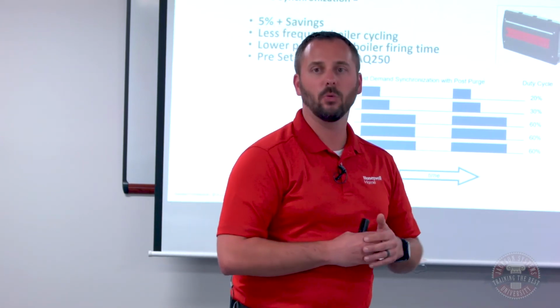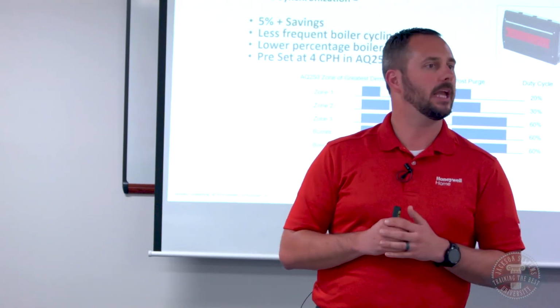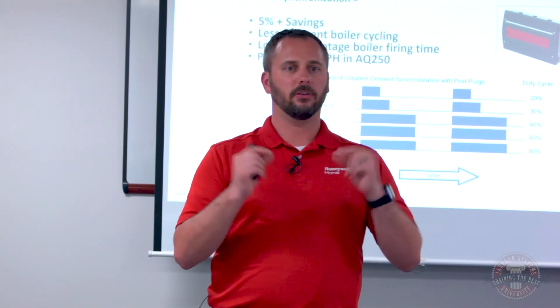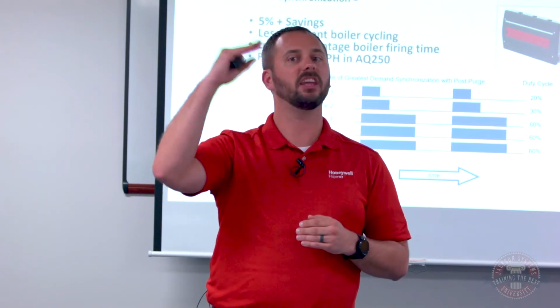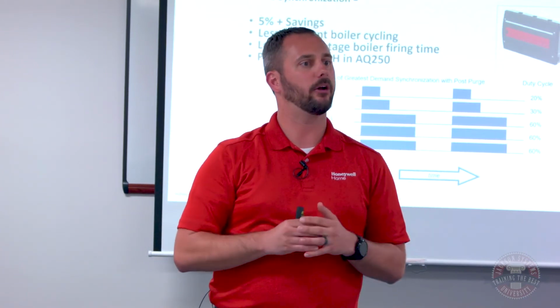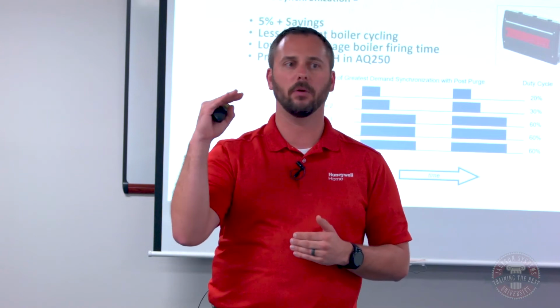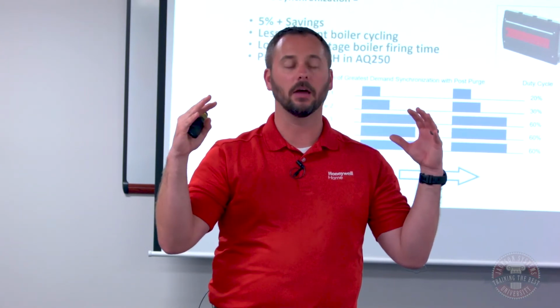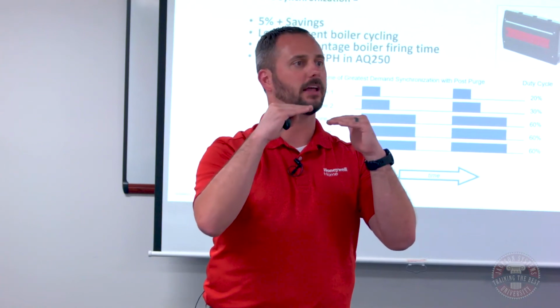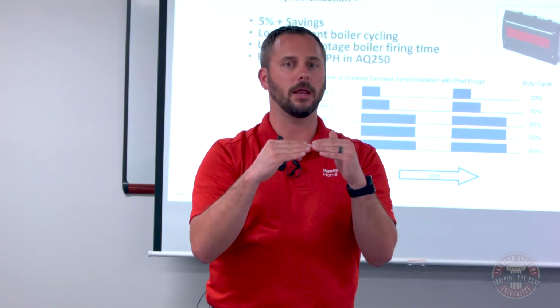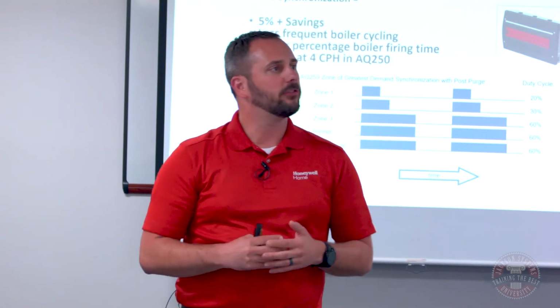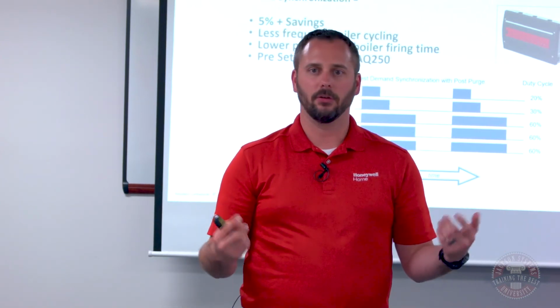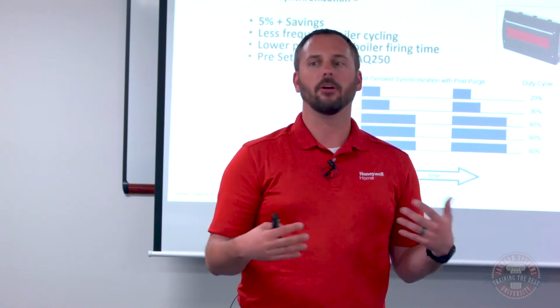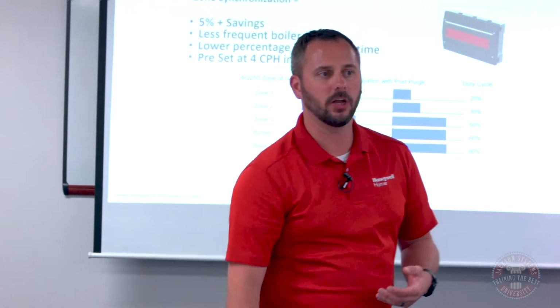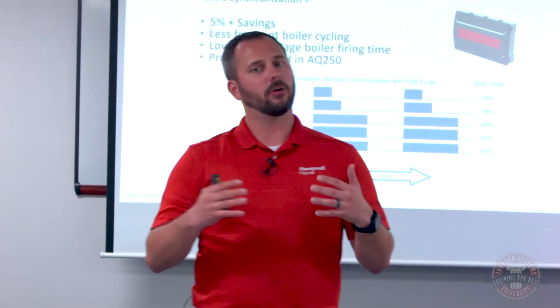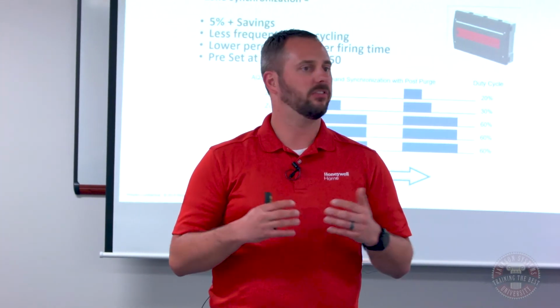So we've got two options and two ways of doing this. The first, we actually have communicating thermostats available that will sense the usage. So it's actually seeing the temperature go up and down and adjusting the firing rate according to that. So if it sees one getting ready to meet, it basically delays it to see if it can get any others. Or when it kicks on, it sees if any other thermostats are close to a call for heat. That's great, but there's a lot of people that don't like communicating thermostats. There's only two that we offer. Maybe they want to use standard, maybe they want to use Wi-Fi, maybe they want to use a high-definition color display. So we went through and retrofitted the device and gave it the ability to operate with standard thermostats.